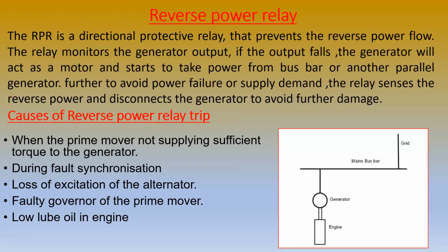So the reverse power has to be detected immediately and the generator has to be disconnected. Otherwise, the ship may go into a full blackout condition. The full power failure may happen and the shutdown of the ship may happen. So before that, we have to know the cause and get the remedy for that, and the reverse power relay has to be activated. Now, the prime mover is not supplying sufficient torque to the generator.